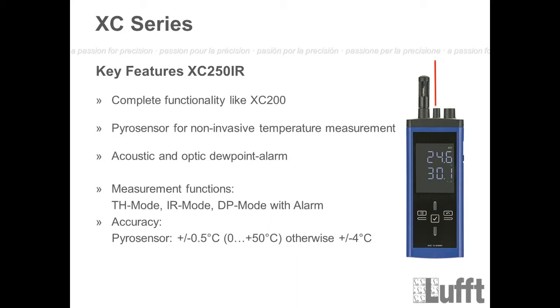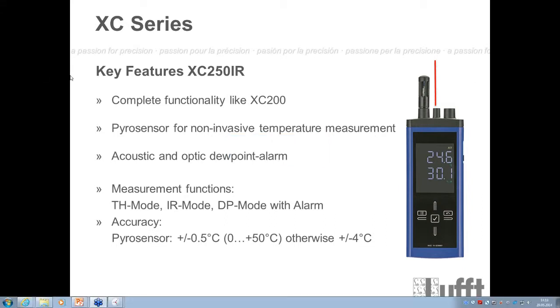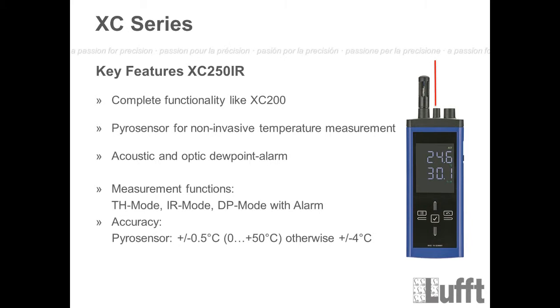Alright, so we have now the XC250, which I want to show you now as a second handheld device. First of all, the functionality of the XC200 I showed you before is completely part of the XC250. So it's the same handheld like an XC200, but you have some additional things here. For the XC250, you have in addition a pyro sensor for a non-invasive temperature measurement. All right, that's an additional thing, and you have the possibility to configure a dew point alarm mode.